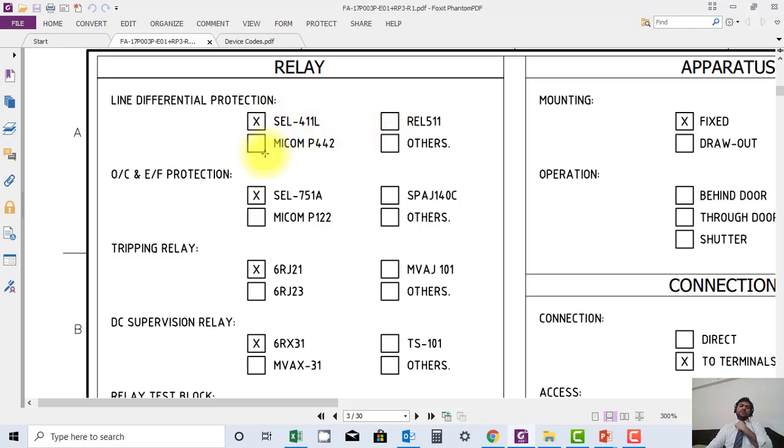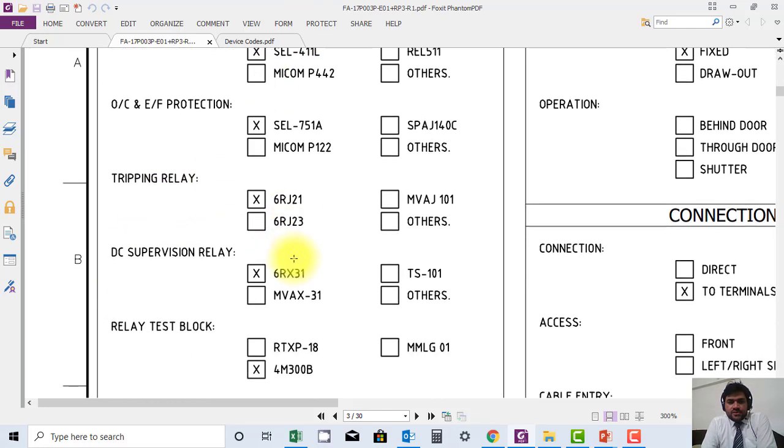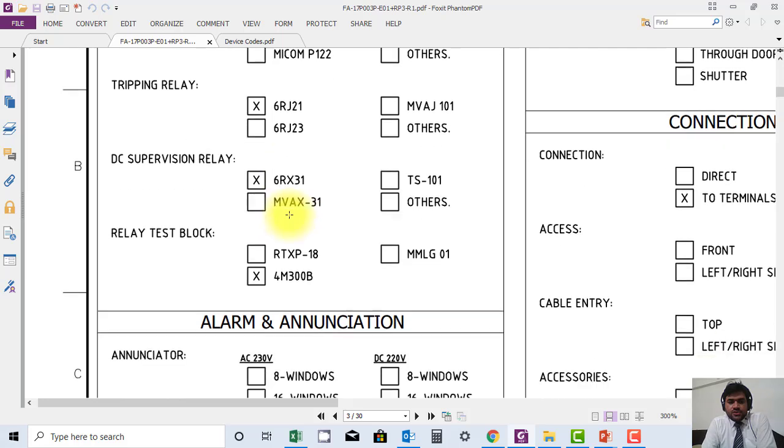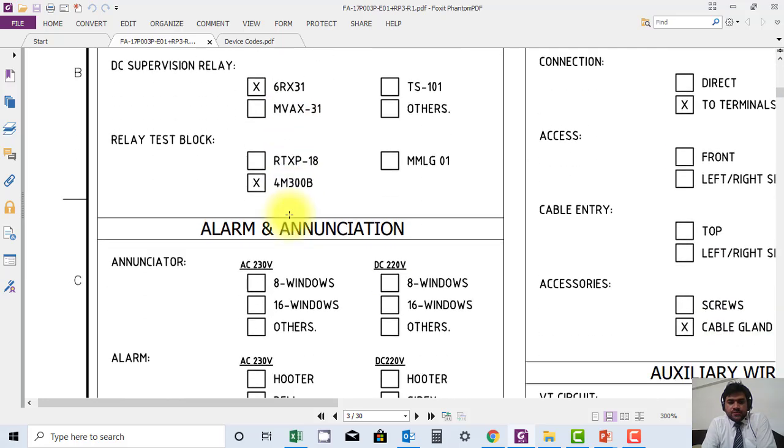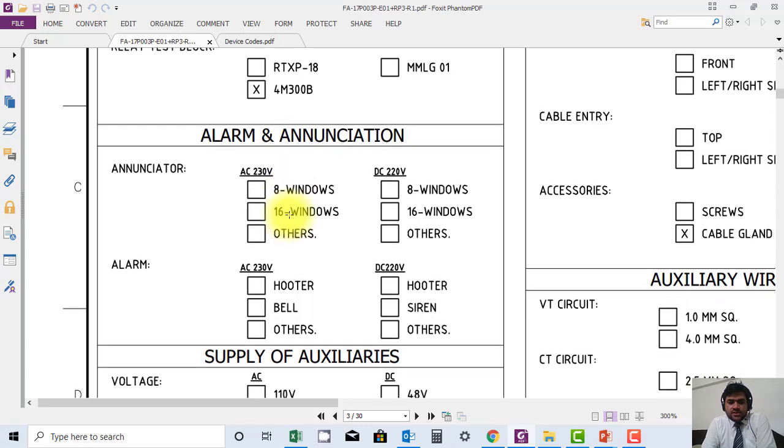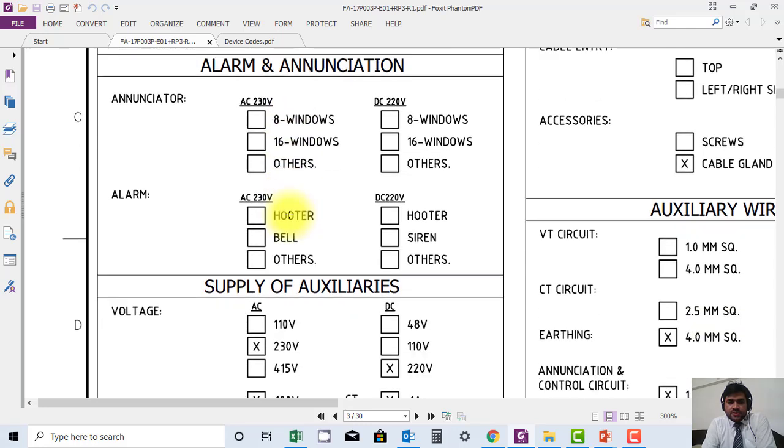Similarly, they have selected all relays which are used: in tripping, which relay is used for supervision. They have also provided detail about annunciators, but nothing is checked here. They forgot to check which annunciator, like 8 window or 16 window, which one is provided.